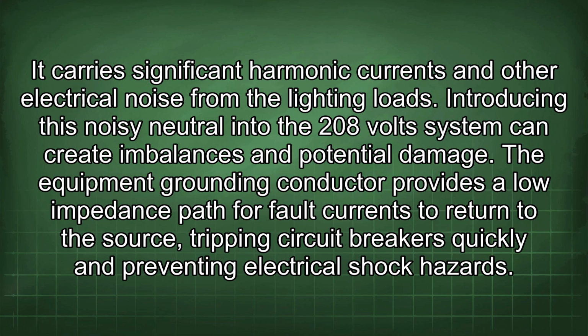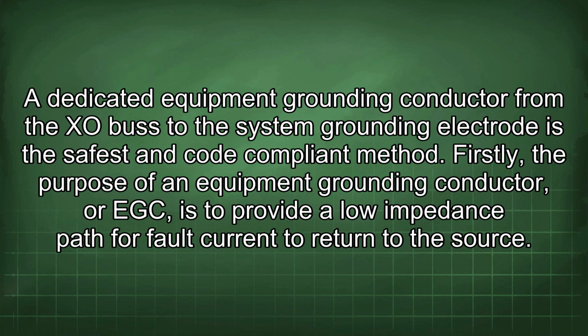The equipment grounding conductor provides a low impedance path for fault currents to return to the source, tripping circuit breakers quickly and preventing electrical shock hazards. A dedicated equipment grounding conductor from the XO bus to the system grounding electrode is the safest and code-compliant method.